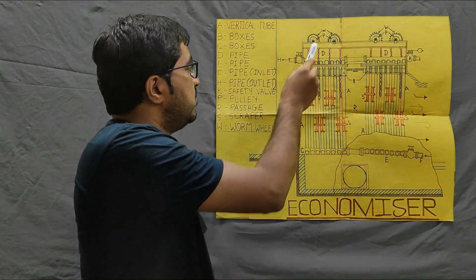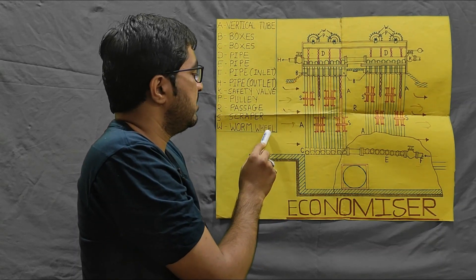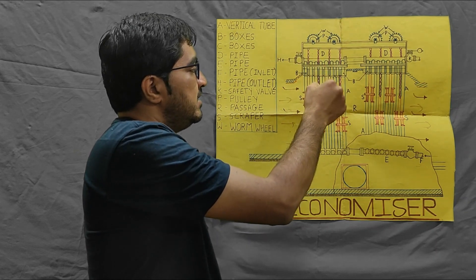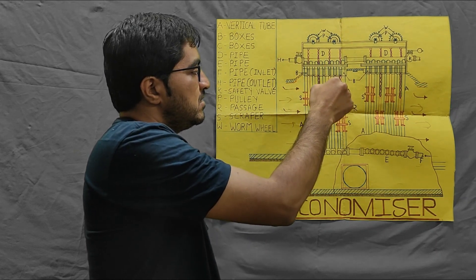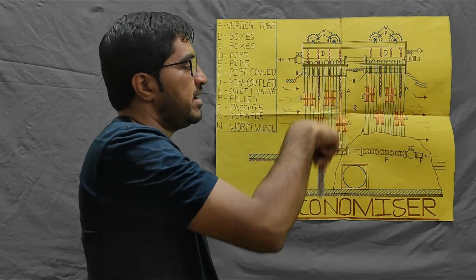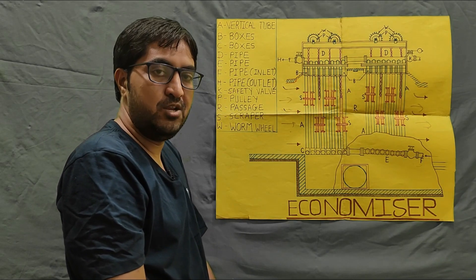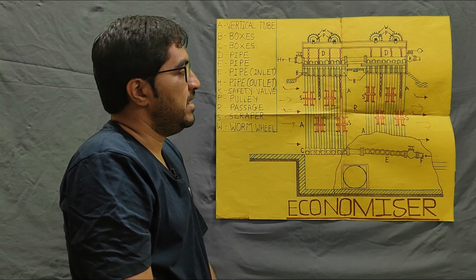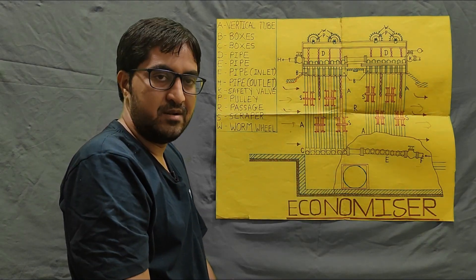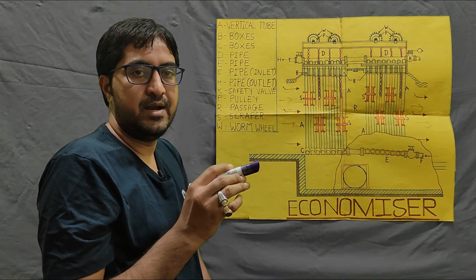Here you can see the pulley — 'W' means it is a worm wheel. The pulleys and worm wheels are connected with chains, and these chains are connected with the scraper. The scraper slides up and down to remove the carbon layer that precipitates on the surface of the tubes, which increases the heat transfer rate.